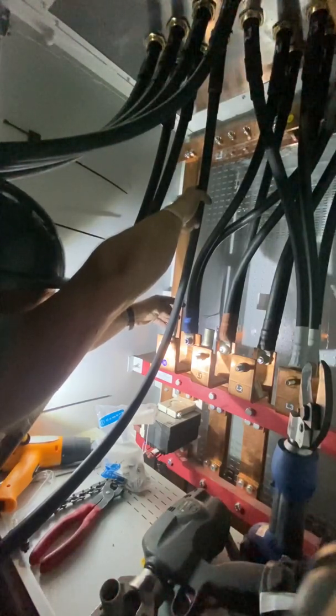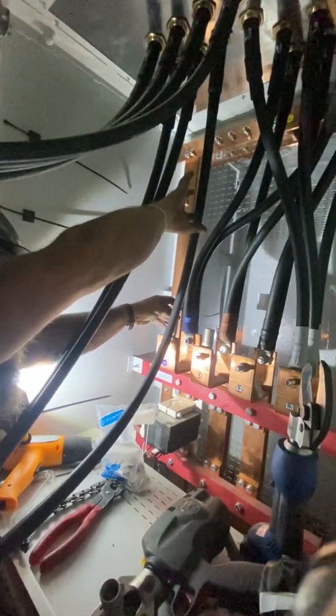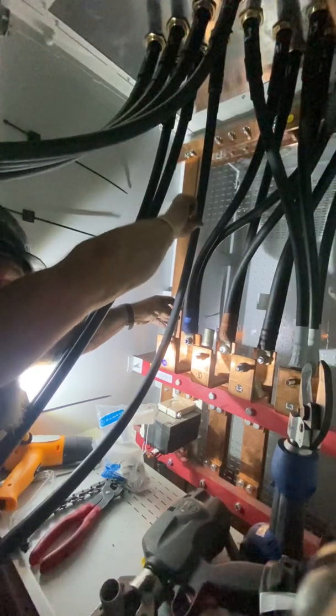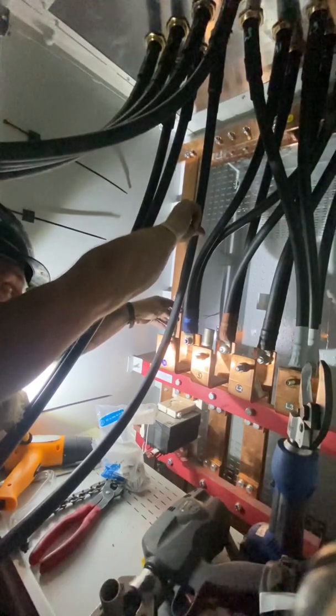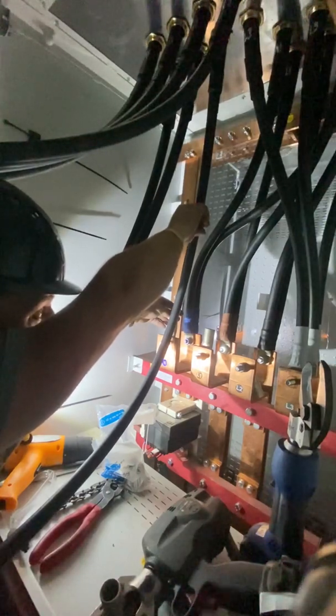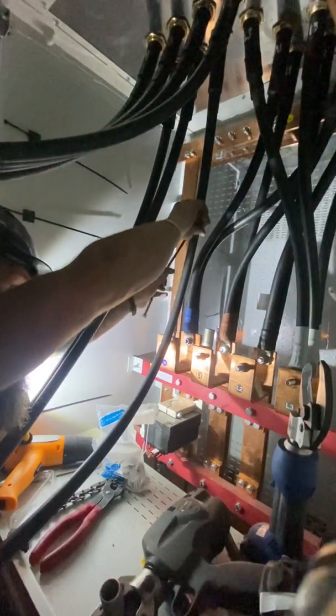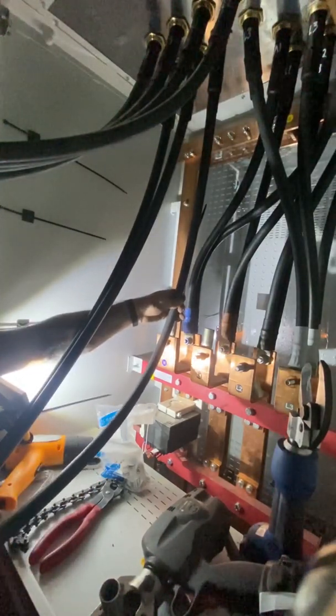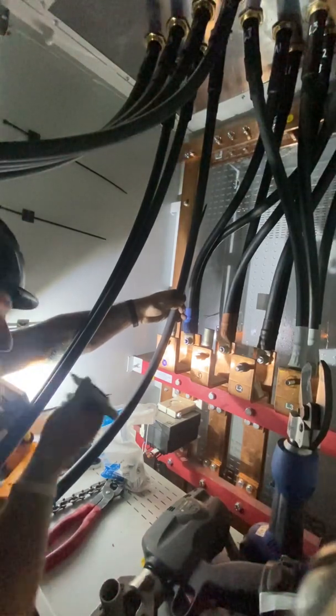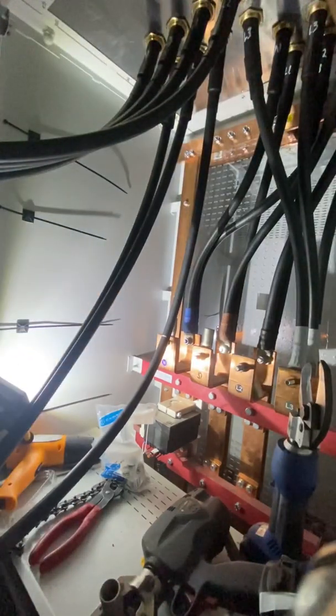I'm going to mimic the shape I want the cable to go. The tie wrap is on the back of the cable - that would be going to the front of the lug, because the lug is facing the other way. Keep hold with that finger, transfer it onto the back, transfer it down and it comes forward. That's my mark.